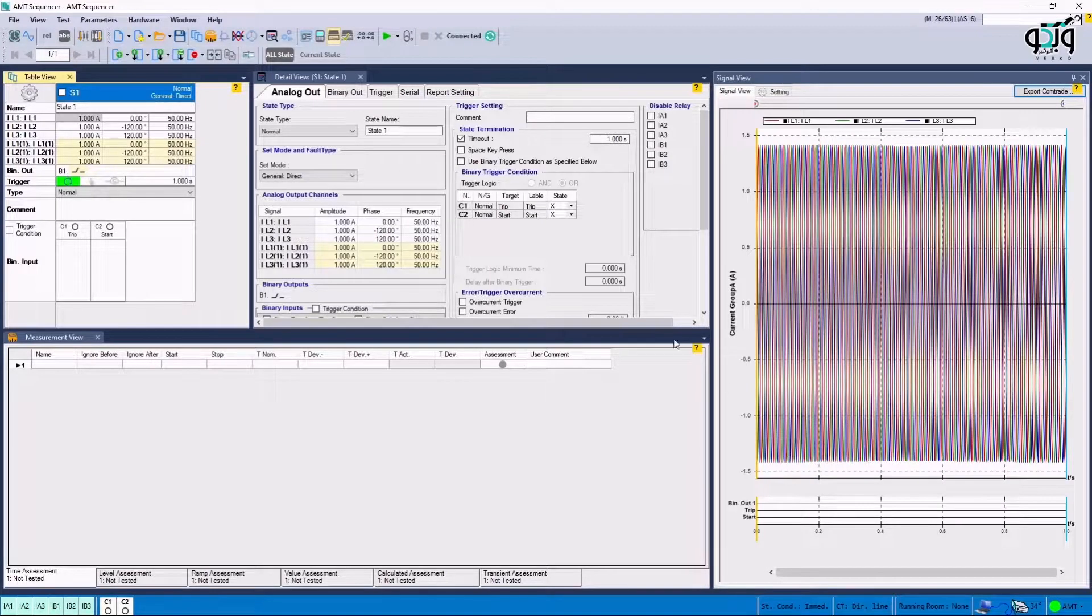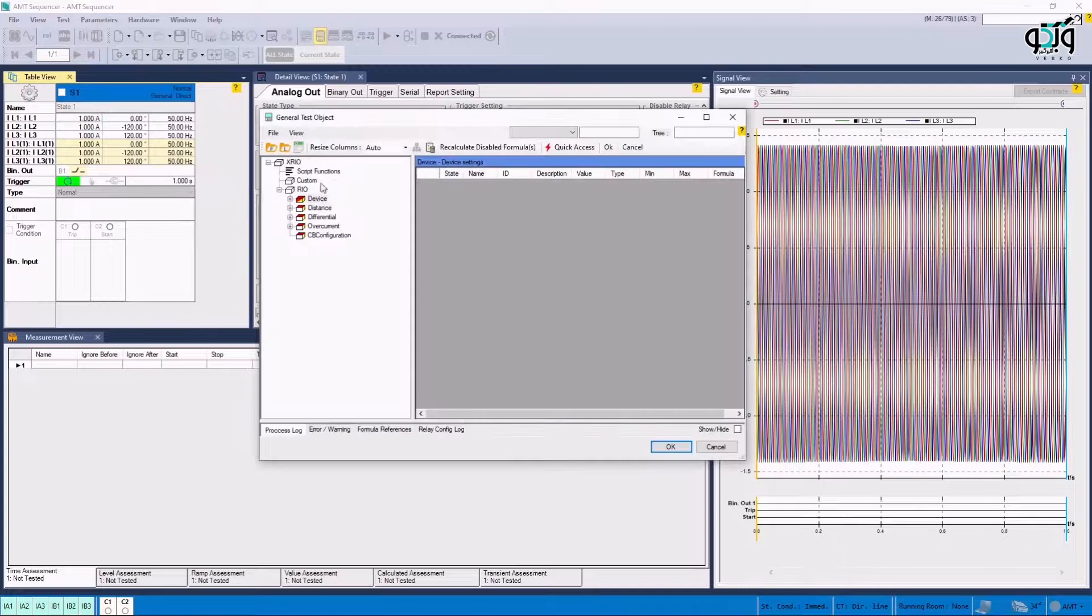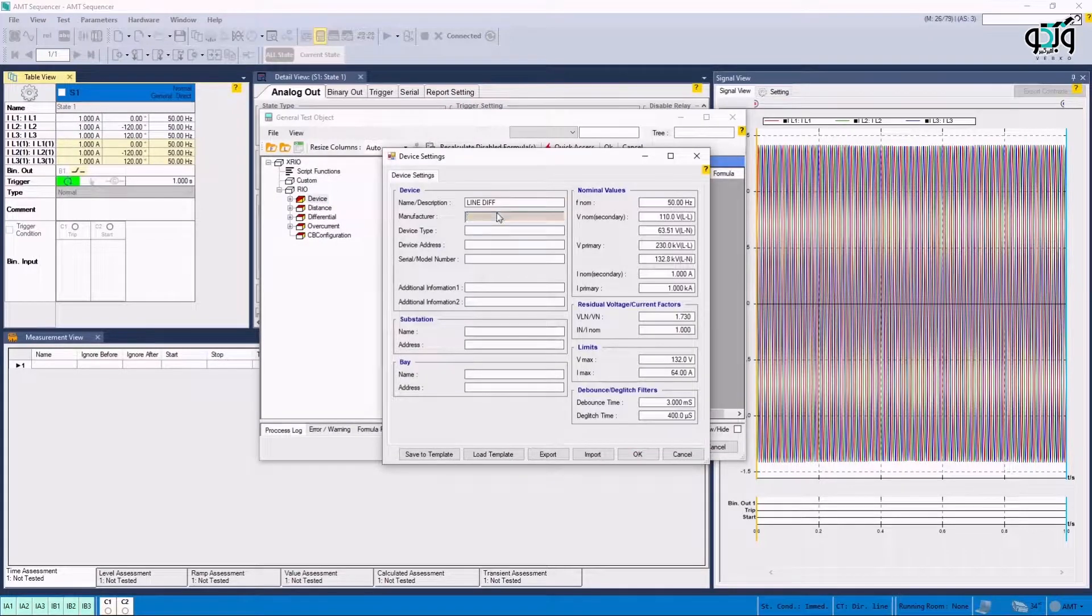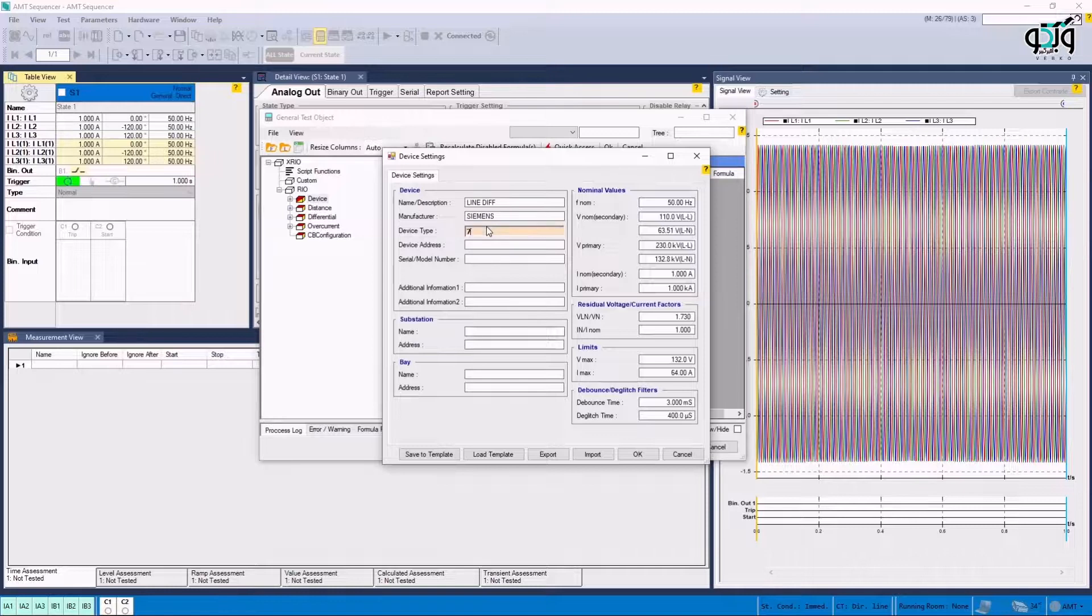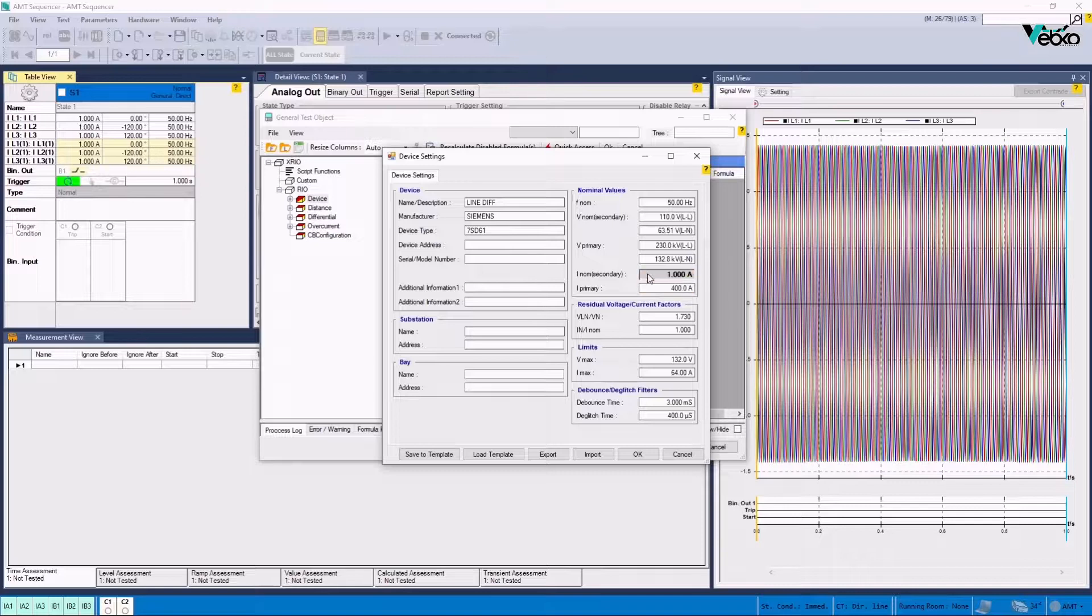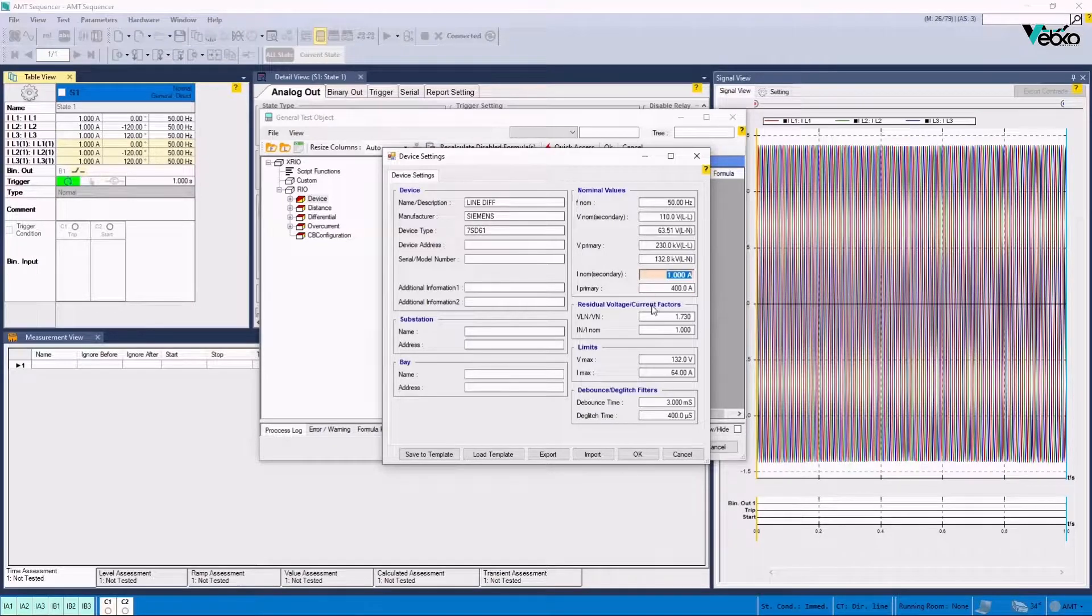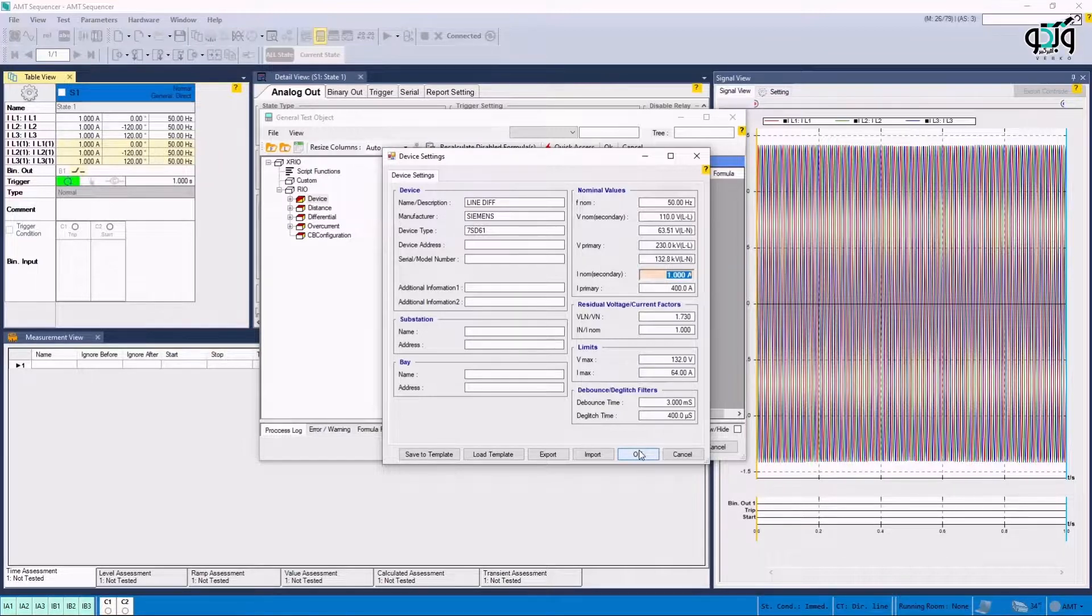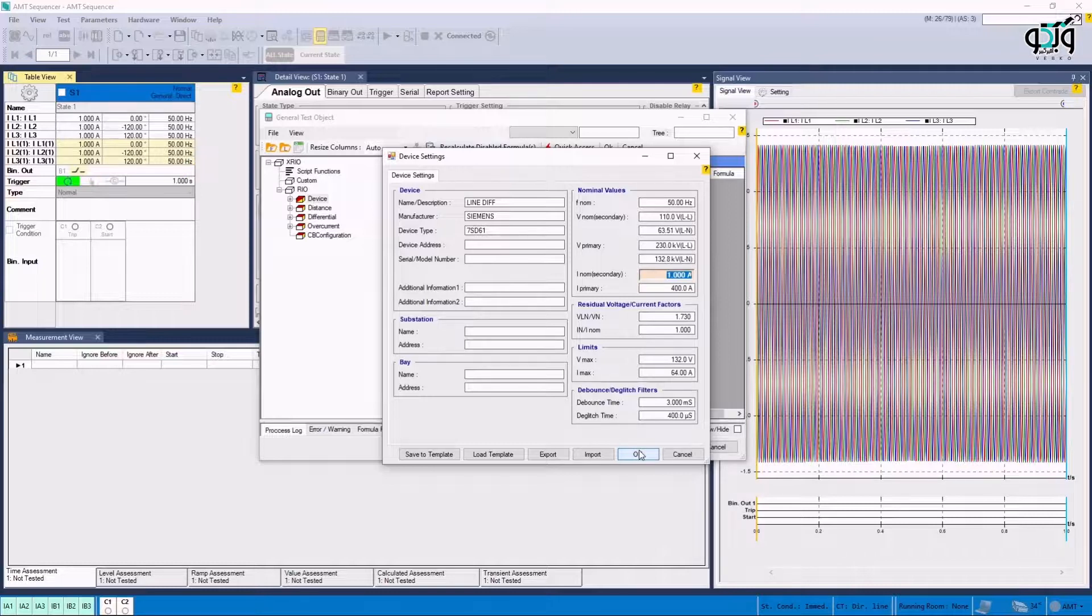By clicking on Test Object Parameters and then clicking on Device, it is possible to enter information about the test such as the title of the test, the manufacturer company, the relay type, the primary and secondary voltages and some other information that are needed in the report. It should be noted that it is possible to add the information related to the rows at the left side of this window after performing the test, but the information related to the rows on the right side must be specified before initiating the test.